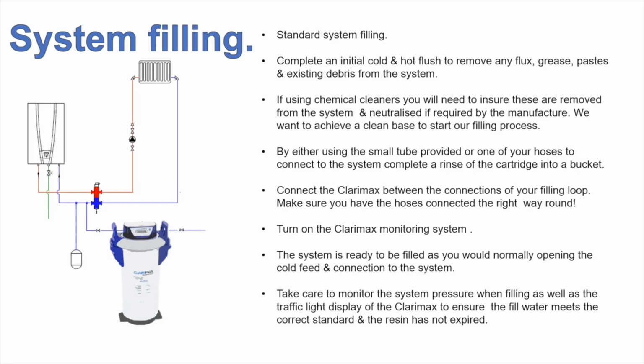We connect the Clarimax in place of where the filling loop would go. We fill the system. Again, we're looking for about an 80% demineralisation and 20% normal water to make sure that we're not at 100% demineralised water. We need to be above 10 microsiemens, but less than 100. After that, guys, you just fill the system as normal, go around venting it, circulate it, test it. We know we're there.